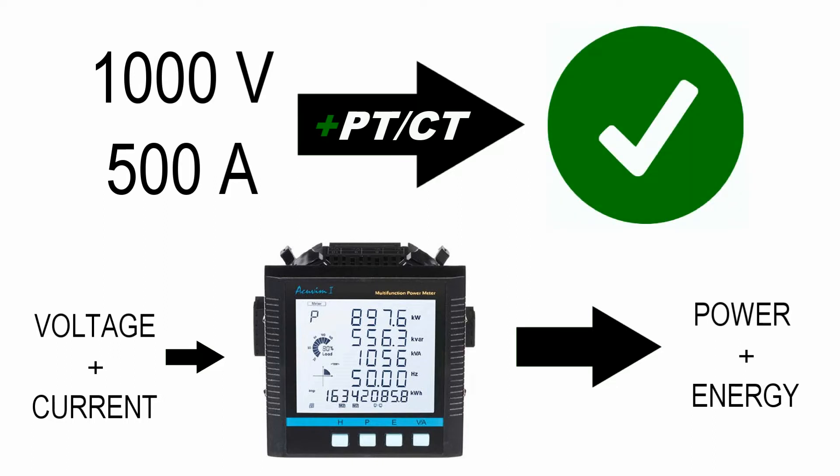As a result, the meter will see the reduced version of voltage and current. In order for the meter to report actual values, installers are required to set up the PT and CT ratio on the meter.